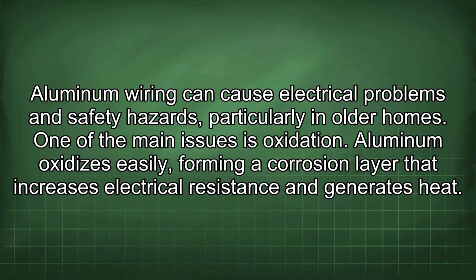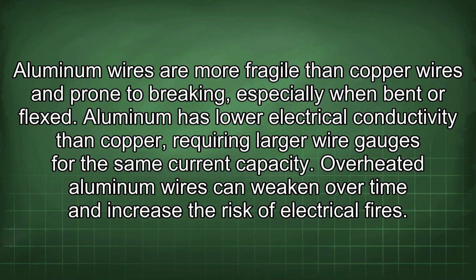Aluminum wiring can cause electrical problems and safety hazards, particularly in older homes. One of the main issues is oxidation. Aluminum oxidizes easily, forming a corrosion layer that increases electrical resistance and generates heat. Aluminum wires are more fragile than copper wires and prone to breaking, especially when bent or flexed.